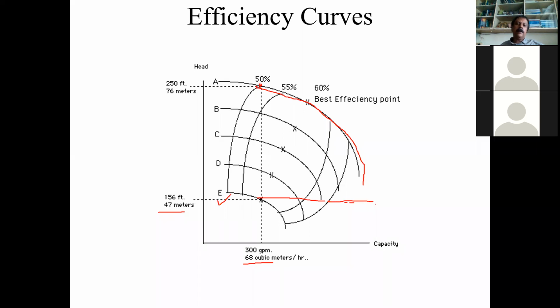What is the impact between A and E? How much will be the difference in power consumption? If you choose A, it will be 31 kilowatt. If you choose E, it will be 16 kilowatt, almost 50% saving. So the right selection of the pump is the key to energy savings.